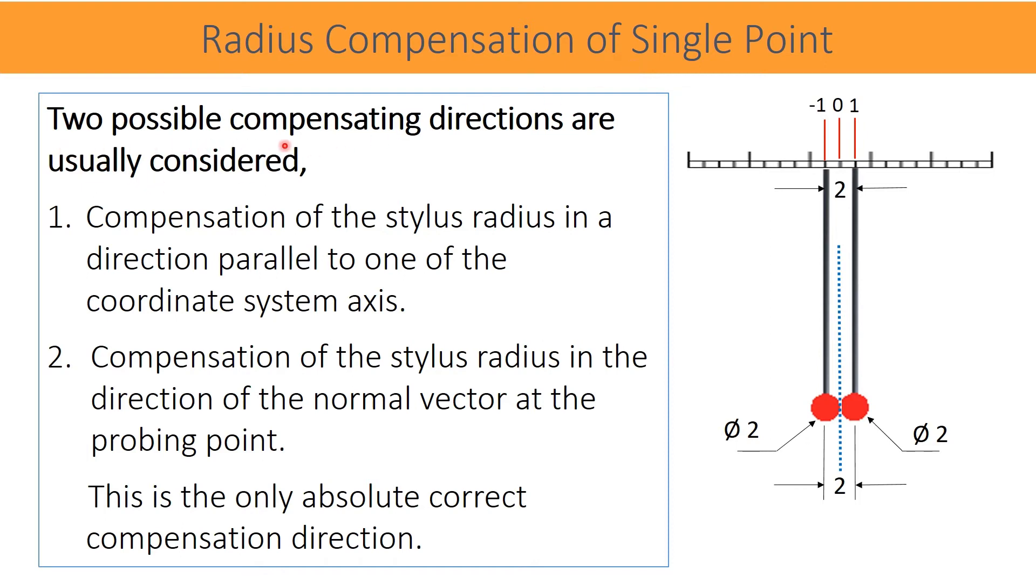There are two possible compensating directions usually considered. First is compensation of the stylus radius in a direction parallel to one of the coordinate system axes. Here, the coordinate system axis is nothing but the part coordinate system.